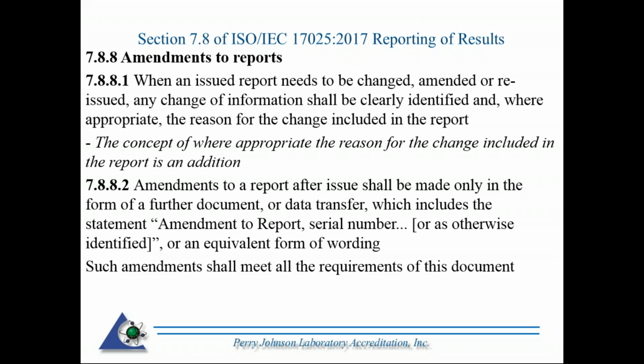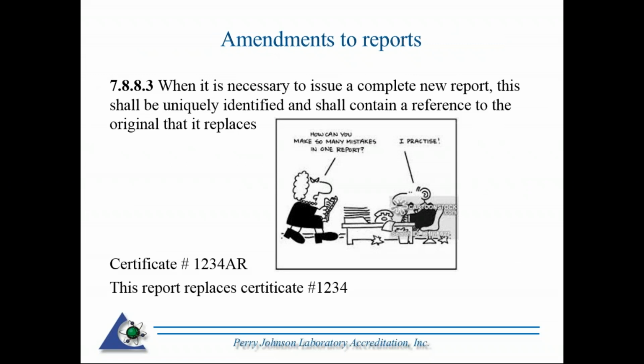Amendments to a report after issue shall be made only in the form of a further document or data transfer, which includes the statement "Amendment to report" or an equivalent form of wording. Such amendment shall meet all the requirements of this document, being 17025. So if you released a report and then you want to change something or add to that report, you'd have to do it within further documentation, and it needs to meet the requirements specified in 7.8.8.2. I know most times in the past I would just issue a new report for whatever reason. So when it's necessary to issue a complete new report, this report shall be uniquely identified and shall contain a reference to the original that it replaces.